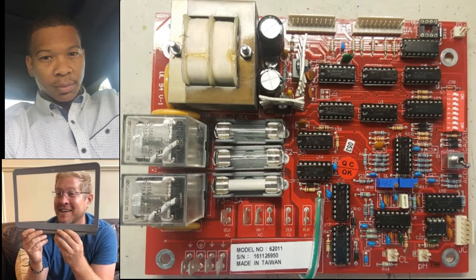Yeah. So diving into a few of these things, obviously we had talked about the relays, and it's an interchangeable part, right? So it's no different relay, whether it's a blue board, a red board, a pH channel, an ORP channel, correct? Right. So if you're having trouble with, let's say, your chlorine feed system, but you know everything is working for your pH, it's fine to start off by changing out that relay, since you know the pH feed system relay works. Right, just doing that by process of elimination.